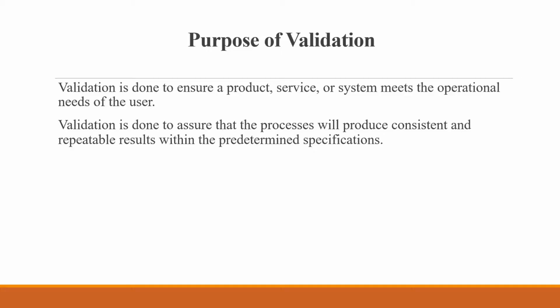As the opposite scenario during validation, you put only one or two units in there, keep it for 24 hours. Will they freeze? If they freeze, or if the temperature becomes very cold because it's alone in there, too cold, it failed validation. So there are many ways of validating our equipment. Do the worst case scenario, the minimum scenario, and the maximum scenario, over and over again.